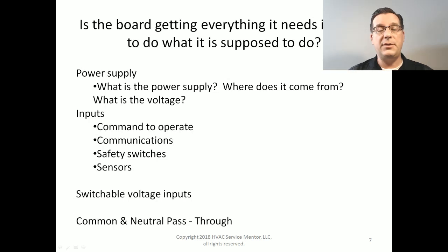Because most circuit boards, well, I shouldn't say most anymore. Maybe it is most still. Most electronic circuit boards in residential furnaces, for example, are going to have more than one voltage landed on them. They're going to have the high voltage and the low voltage. Same thing is true for smaller, residential style packaged units that have a furnace and AC in one complete box. They're going to have multiple voltages landed on a control board, sometimes as many as 3 different voltages. So you need to know which one of those voltages is the one that powers your control board, because it's not going to be all of them.